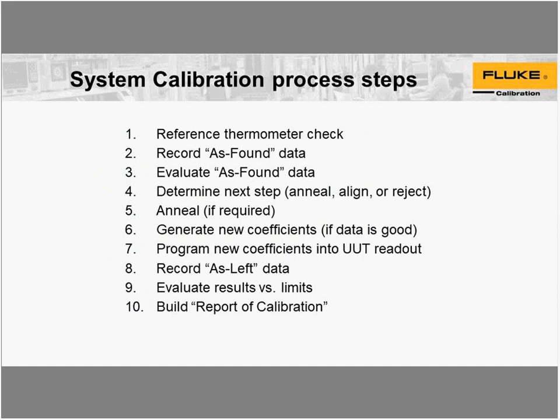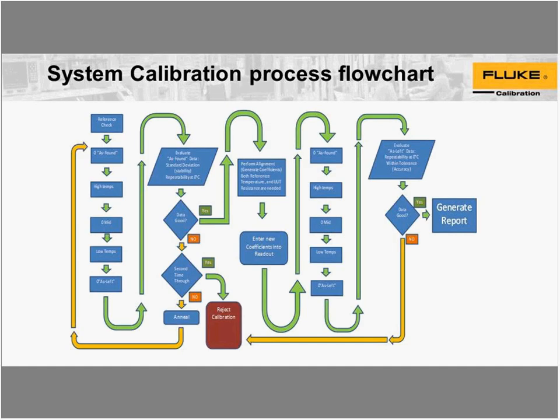All right, let's get into our process steps for doing system calibration. The thing we want to do is a reference thermometer check. Then we want to record the as-found data and evaluate it. At that point, we determine the next step, whether we're going to anneal it, align it, or reject it. Anneal if required. We're going to determine the new coefficients if the data is good, and we'll program the new coefficients into the readout. Then record the as-left data. Then we'll evaluate those results versus the limits, and if we're ready, then we'll go ahead and build a report of calibration. Now, this flow chart shows the whole process. So let's get into it.